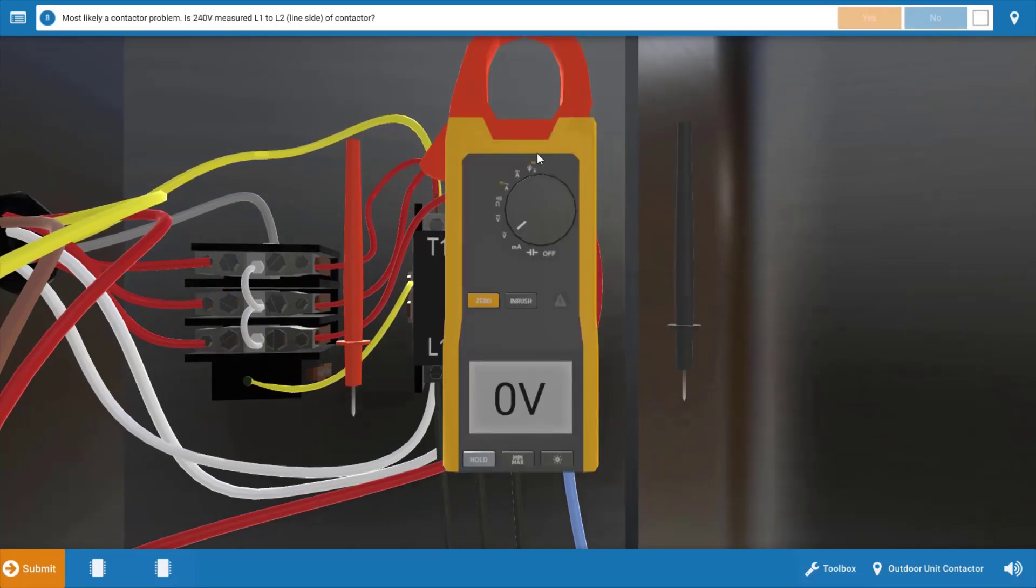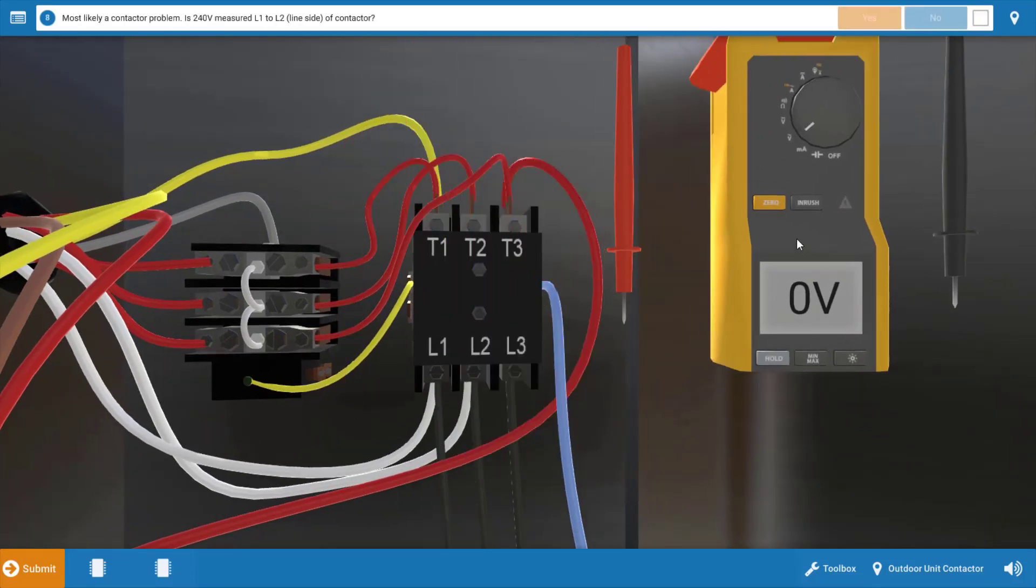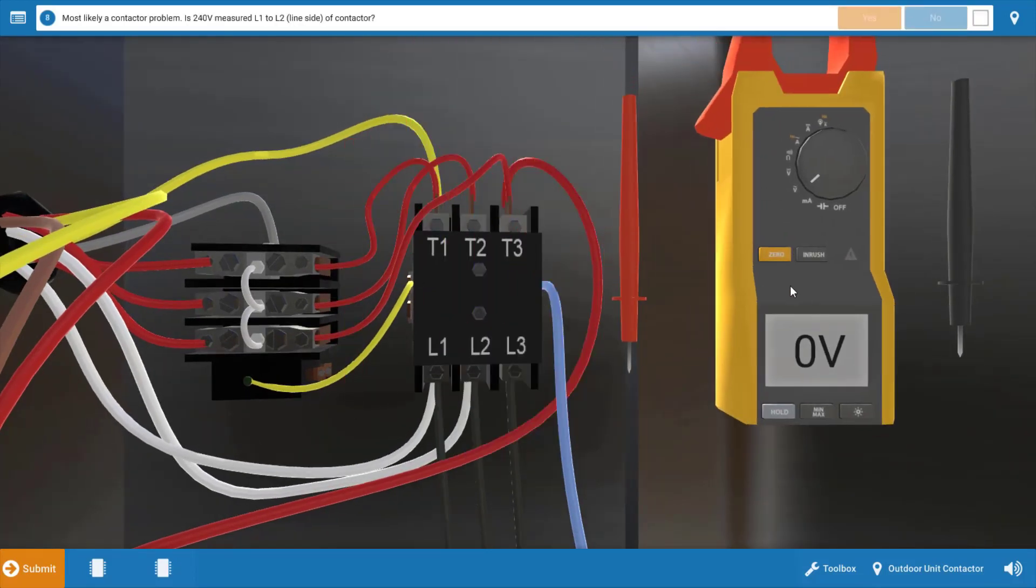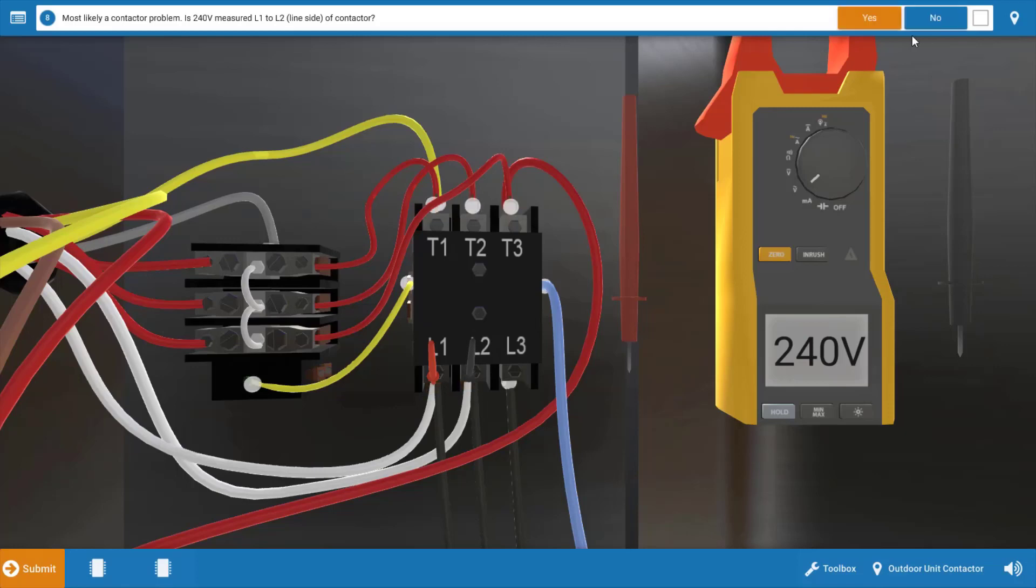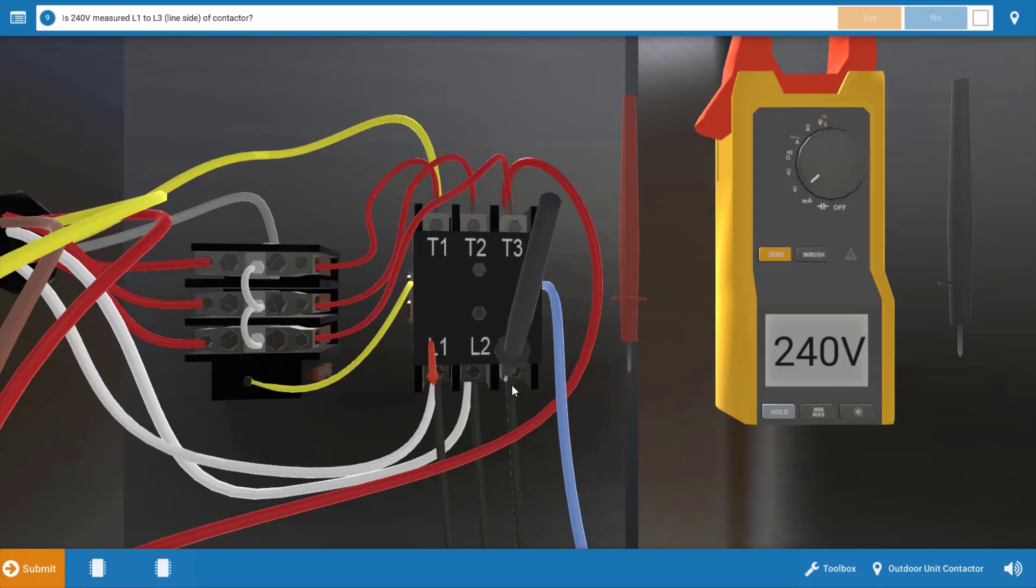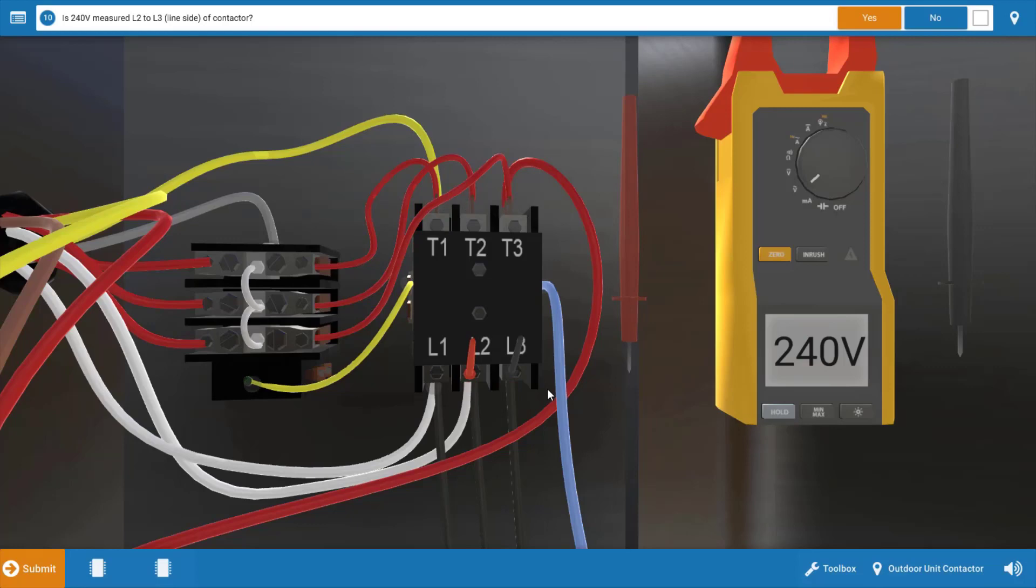Now, our next step is we're going to check to see if we have 240 volts coming to the line side of the contactor. Now, this is here at the bottom, so we're going to drop our leads at L1 and L2, and we have 240 volts there, so we can click yes on the procedure guide. Now, we're going to check L1 to L3, and we have 240 volts there as well. Again, click yes, and last but not least, we're going to check the other phase of power, L2 to L3, and we have 240 volts there. So we do have line voltage coming in at the contactor.